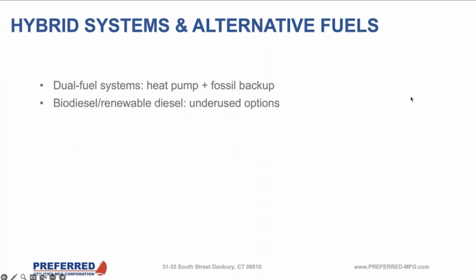The real difficulty with condensing boilers is you're condensing in the stack, so the products of combustion are acidic, and you have to make the stack out of very special materials. But I don't see biodiesel being any more acidic than number 2 diesel, maybe even less so. I would assume it would be less. And the burners can burn biodiesel, so I think it's just a matter of people generating the demand.